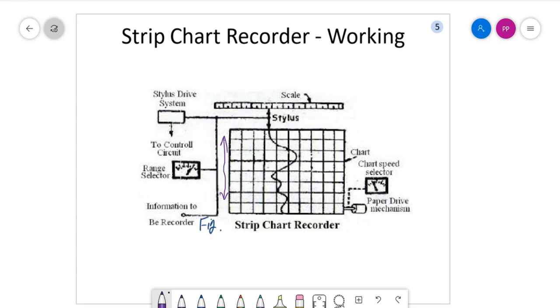Once we decide the direction of movement through this paper drive mechanism, we can determine that with the change of time, the data will be recorded. The printing mechanism is along the x-axis of this figure where you can see recordings of the measures, while the y-axis is basically the time slot. The paper drive mechanism includes a paper roller where the strip chart in big length is rolled, and a pinch roller which controls the speed of movement of the chart. There are slots on the chart with special scaling, according to which the rate of movement of the strip chart is determined.